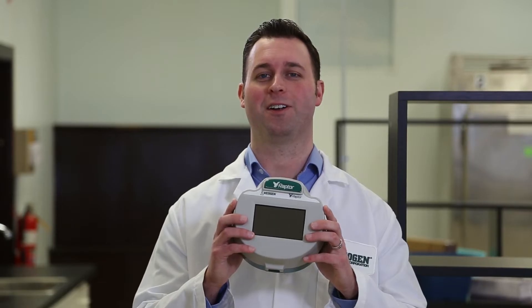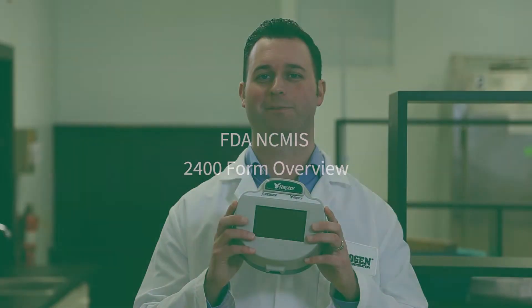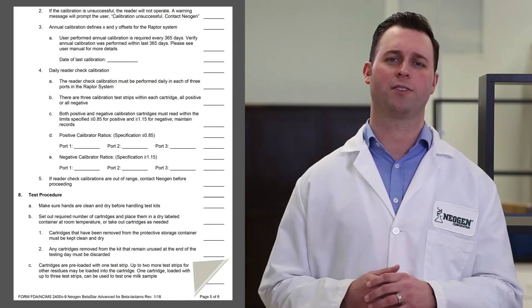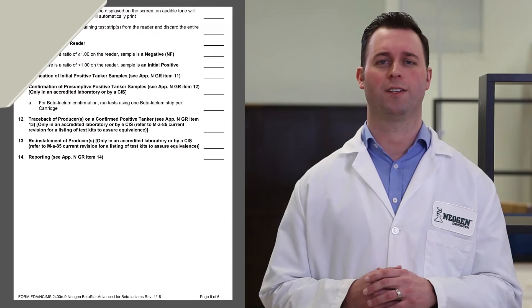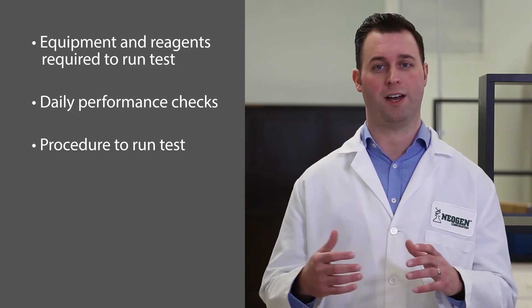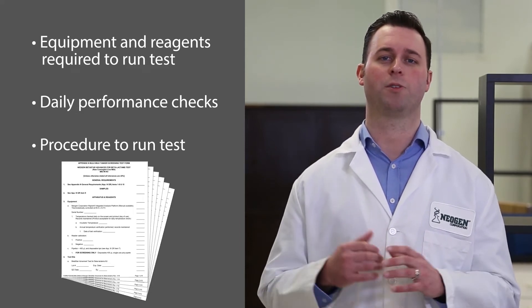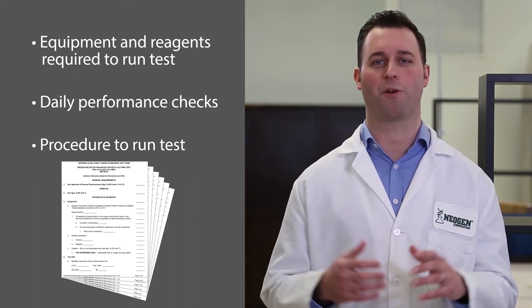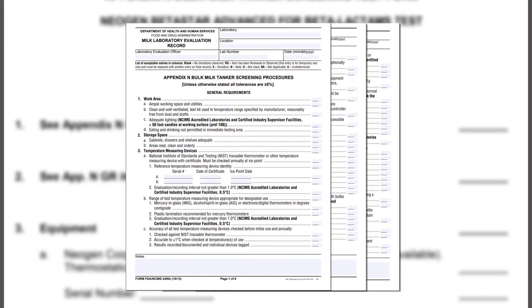This concludes the overview section of the Raptor Integrated Analysis Platform. Most FDA 2400 forms may seem intimidating at first, but once you understand the overarching concepts within the form, it's easy to follow. The form is broken into three sections: the equipment and reagents required to run the test, the daily performance checks, and the procedure to run the tests. There are 14 bolded sections within the BetaStar Advanced for Beta Lactams 2400 form. The first section specifies general requirements for antibiotic testing applicable to this 2400 form, referenced in the first two sections. The Appendix N general requirements form can be found on the FDA.gov website.